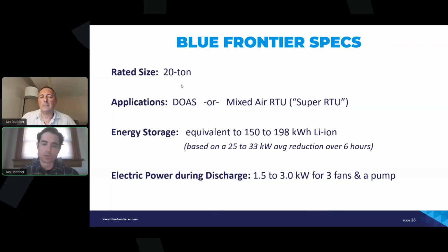same amount of ventilation. Energy storage-wise, we benchmark ourselves against what the DX-DOAS system would have used over that 6 hours. And so based on what we're seeing of a 25 to 35 kilowatt average power reduction over 6 hours compared to a typical DX-DOAS system, this translates to about 150 to almost 200 kilowatt hours of what a lithium-ion battery would have to provide from a storage perspective. And then the final metric to point out is the electric power during discharge. So here we have 1.5 to 3 kilowatts is all the power we use during our 6-hour discharge event. And that's just to power three fans and a small desiccant pump.